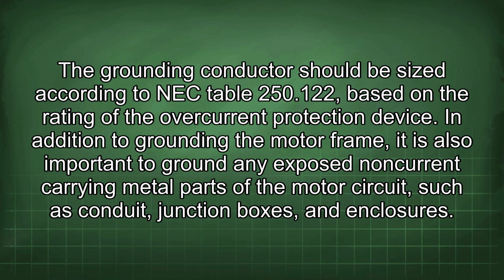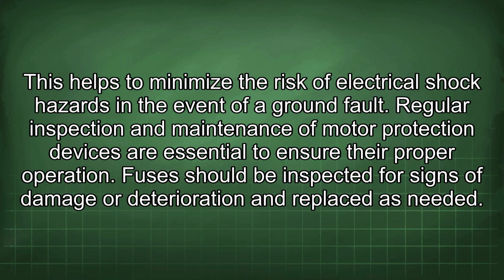In addition to grounding the motor frame, it is also important to ground any exposed non-current carrying metal parts of the motor circuit, such as conduit, junction boxes, and enclosures. This helps to minimize the risk of electrical shock hazards in the event of a ground fault.